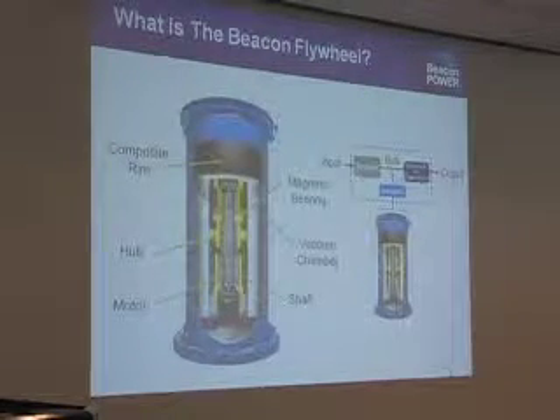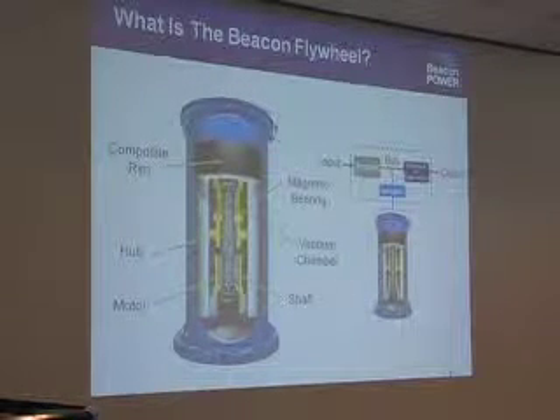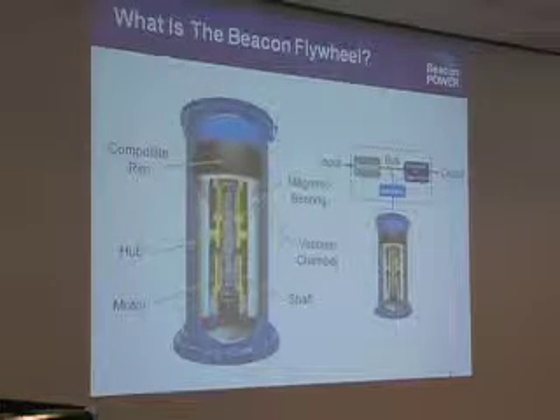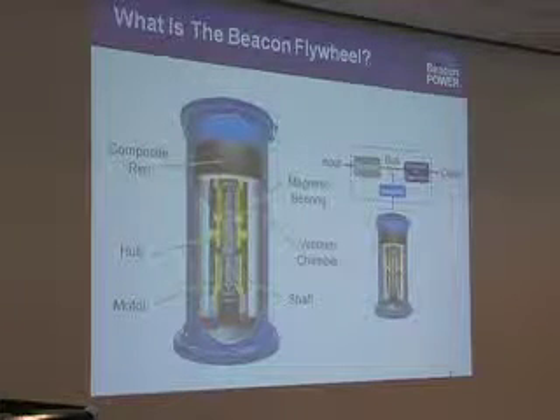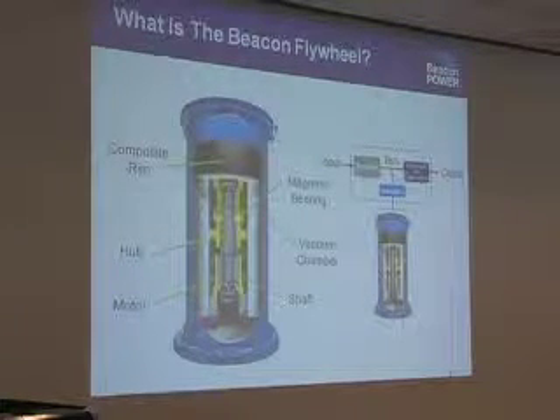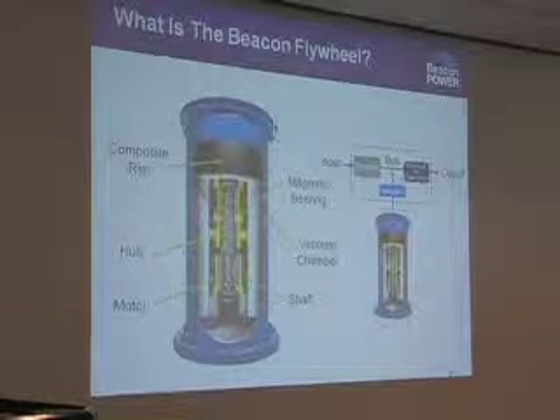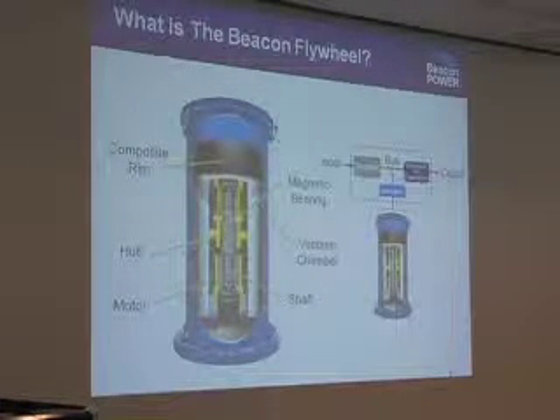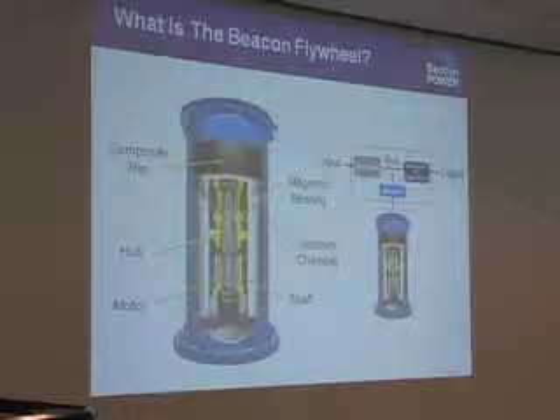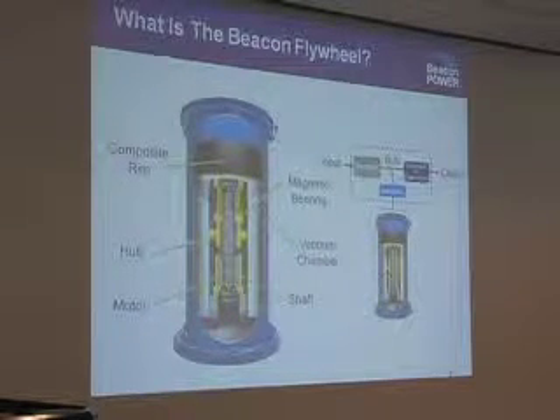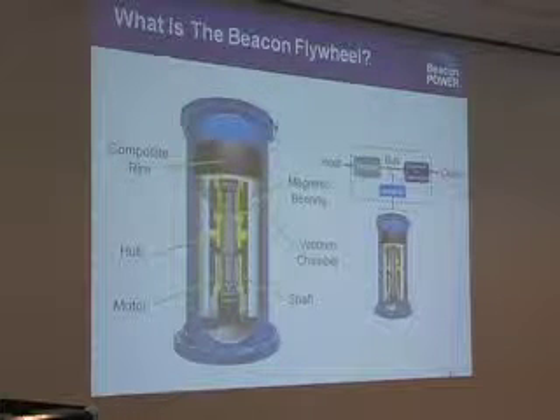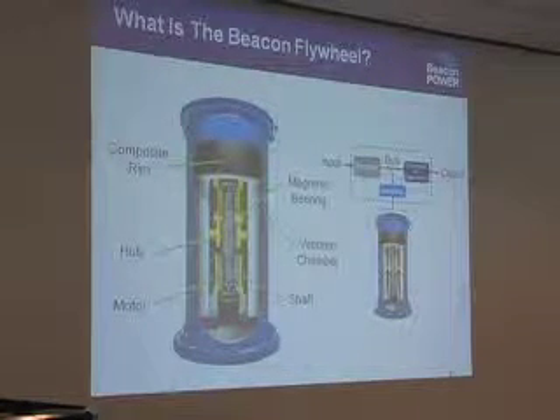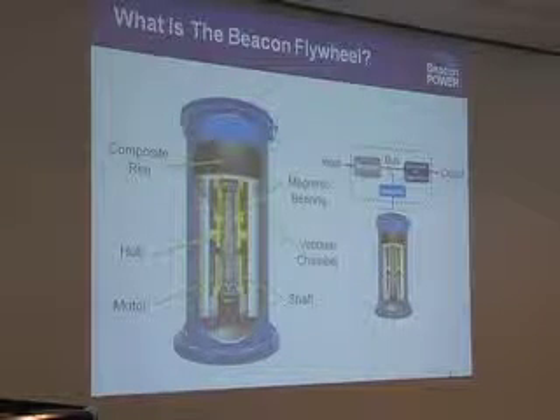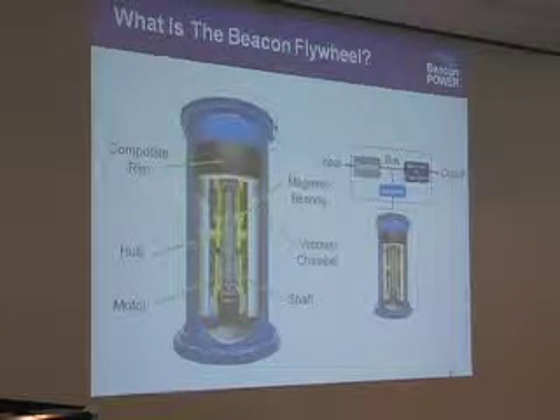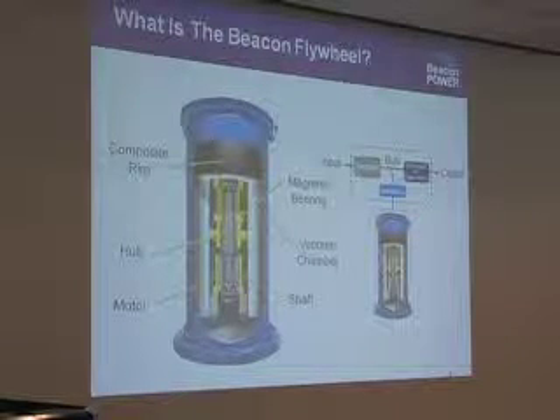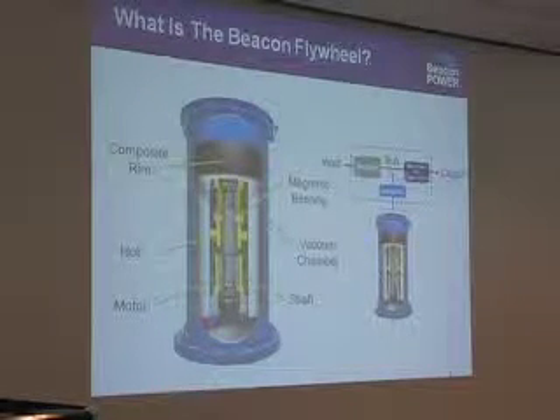So a little bit about what a flywheel looks like. This unit, if you've seen it out at the poster, is about 7 feet tall. Inside that blue container, we have a composite rim that's spinning, as Andrew likes to describe, essentially the mass of an automobile going Mach 2. It's about 10,000 pounds, spinning at 16,000 RPM. Each one is 100 kW or 25 kWh, and 10 of them makes a megawatt. That blue casing provides a vacuum seal, and the units are on magnetically suspended bearings, just going around and around.